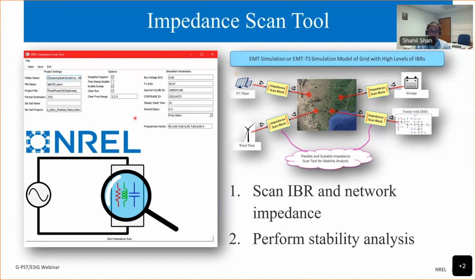The GUI, or this software, will perform the impedance scan, and it will scan the impedance of both the PV plant as well as the network. Then I use that scan data to perform stability analysis. We can repeat this process at other IBRs. Not just a single plant, we can also use this tool to understand the impact of a feeder with 100 DERs on the stability of a wider transmission network. So this gives you the ability to zoom in on the network because you can really place this tool anywhere.